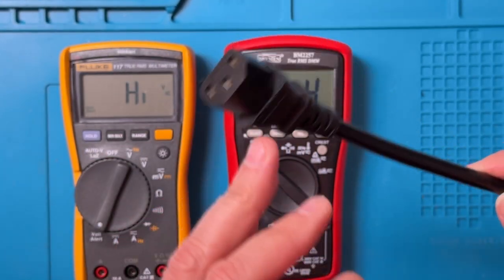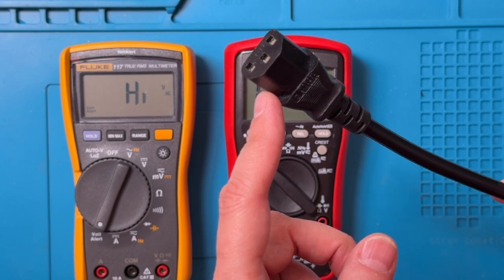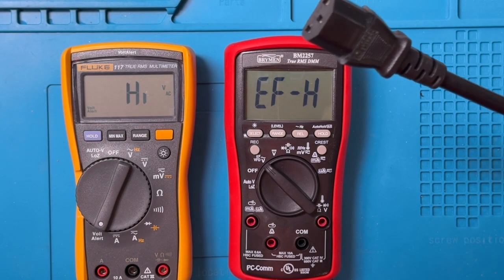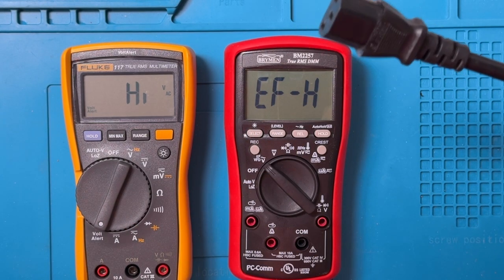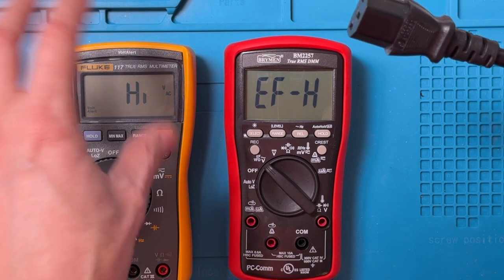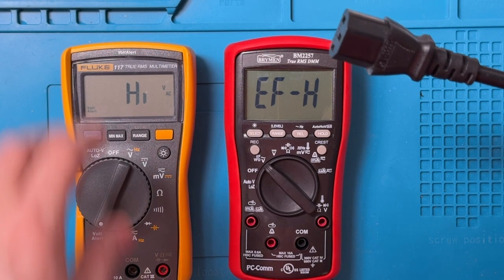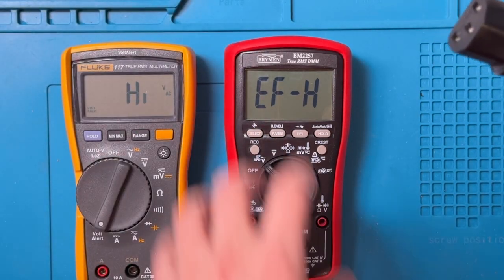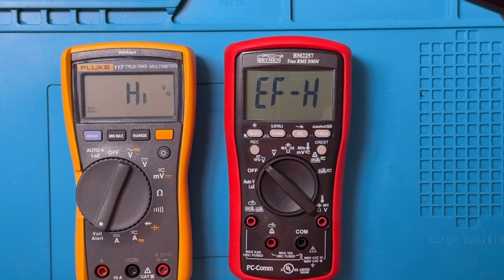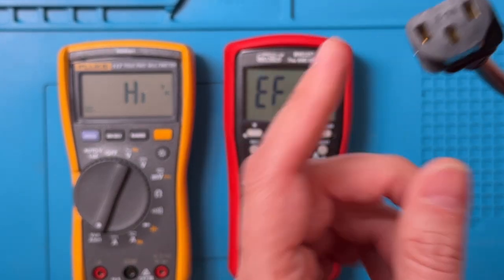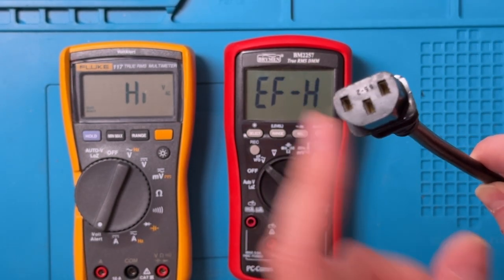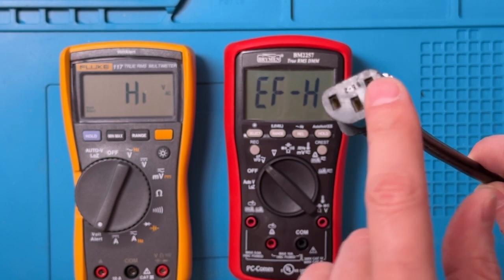Now in terms of non-contact voltage, my general approach is to take this plug and bring it to where the non-contact sensor is for these meters. On the Fluke, it seems the sensor is right at the front, and I think for the Brymen the sensor's at the front as well, and the hot line runs along this edge of the plug, this being the ground and that being the neutral. So this is where the hot line is.